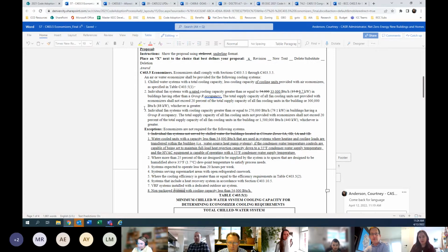Right, in number 2, any building with a total of 300,000 BTU of cooling is going to require an economizer. With number 3 there, I think you've got that covered. Okay, yeah, because it went down—the old code was 300,000, I think now in 2021 it's 270,000. Is that right? That changed, didn't it?